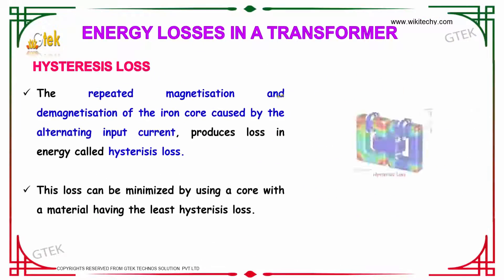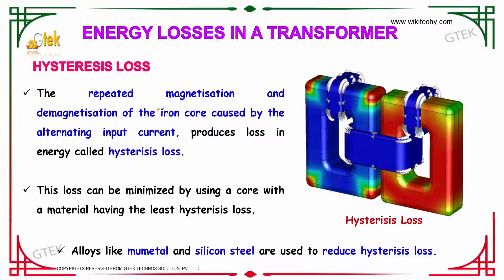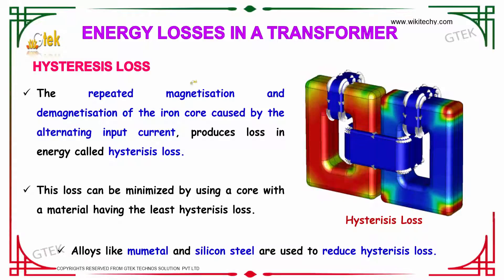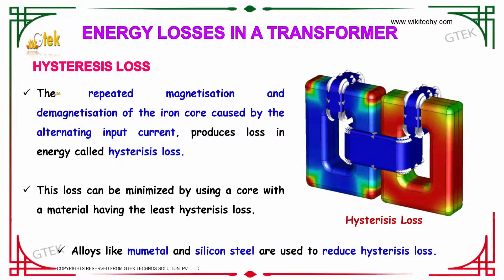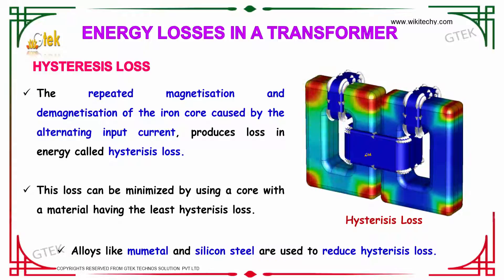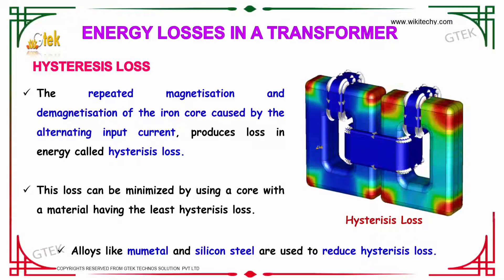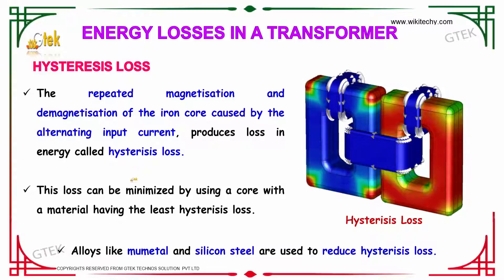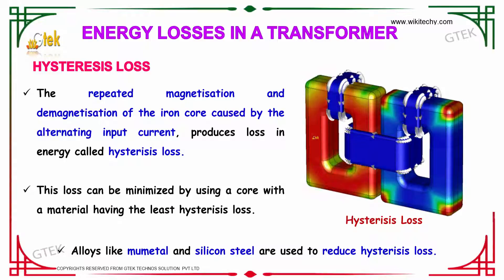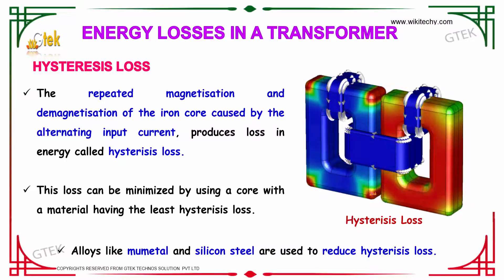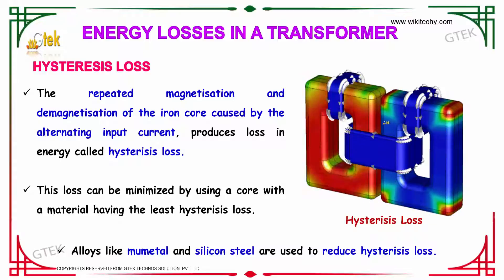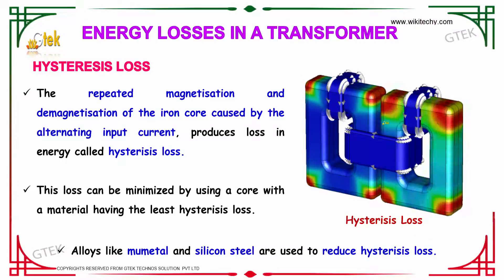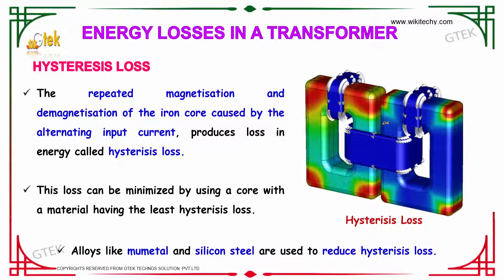What are the losses? The first loss is hysteresis loss. The repeated magnetization and demagnetization of the iron core caused by the alternating input current produces a loss in energy. This loss can be minimized by using a core material having the least hysteresis loss. Alloys like mumetal and silicon steel are used to reduce the hysteresis loss.